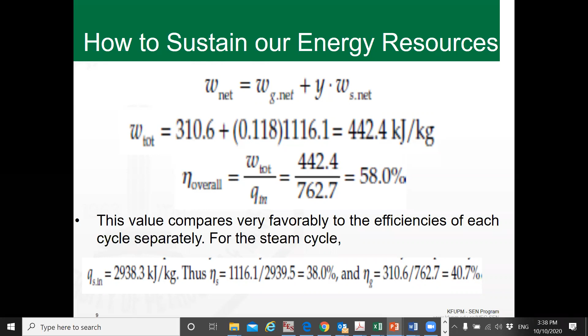So this is the economic side. In case you upgrade a plant, like you have a gas turbine alone, a power plant started maybe 16 years back with gas turbines only, then they added a combined cycle to it. It was built and designed to be extended with a heat recovery steam generator at the exhaust of the turbine instead of going directly to the chimney. They even have a bypass, so they can bypass the heat recovery steam generator and go to the chimney directly, or if more load is needed, they run it through the heat recovery steam generator.